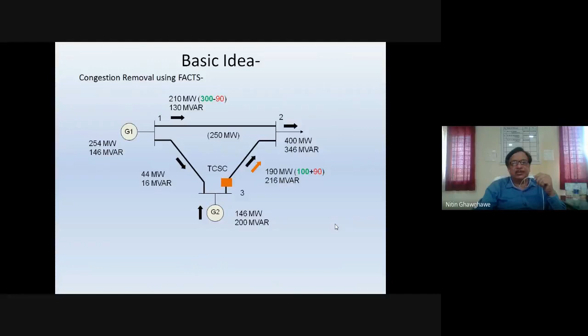In this way, the congestion in the network can be removed by using the FACTS devices. What these FACTS devices have done is just divert the load flow. There is a diversion, a redistribution of the load flow. Power generation is the same, demand is also the same. Only by introducing this TCSC, without using an extra line, because it is not possible to install an extra transmission line between the two nodes or buses. So this is how the situation can be controlled in deregulated systems, especially as regards the network condition.